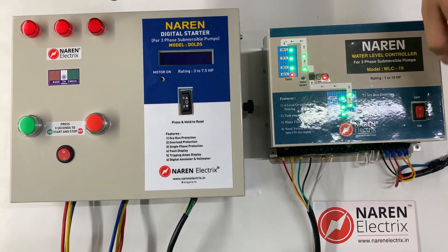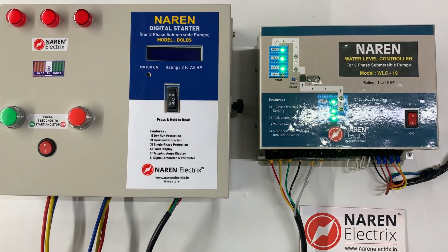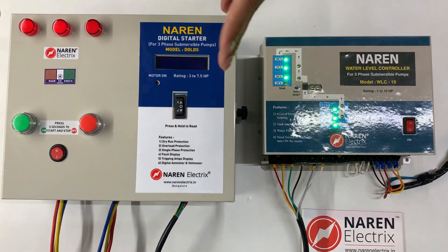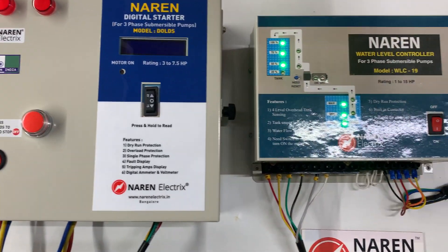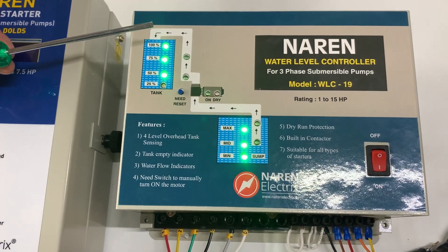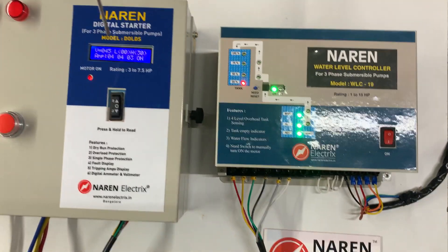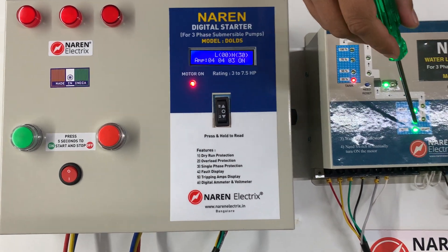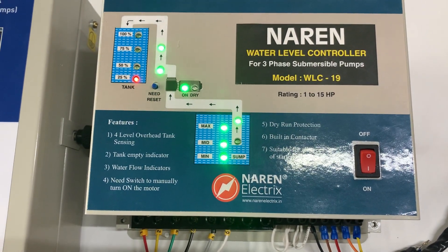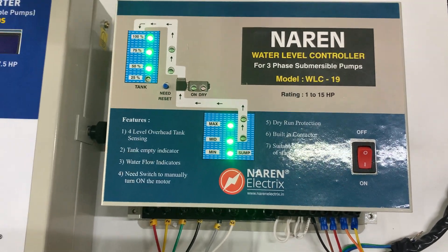We will now power on the system. The RYB phase indicators are displayed on the starter panel, and the water levels are indicated on the water level controller. You can see the water levels in the overhead tank dropping, and the moment the water level goes below the 50% mark the motor is turned on — the tank-empty indication appears. The moment water hits the dry run sensor, the flow indicators pop up, and when the overhead tank fills up the motor automatically switches off.